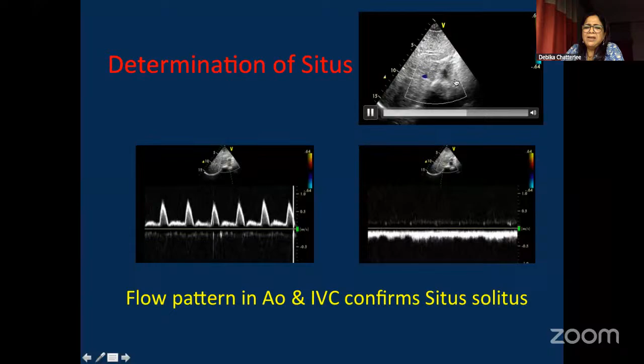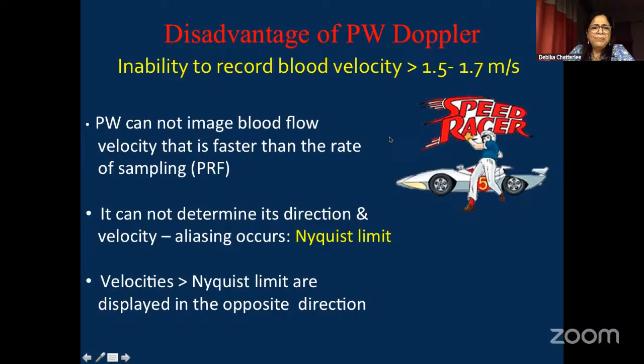But pulse wave Doppler has a disadvantage. It is unable to record a blood flow velocity of more than 1.5 or, say, 1.7 meters per second. This is the limit of the pulse wave Doppler. It is called the Nyquist limit. If a particular patient has a velocity more than this, you will get aliasing.